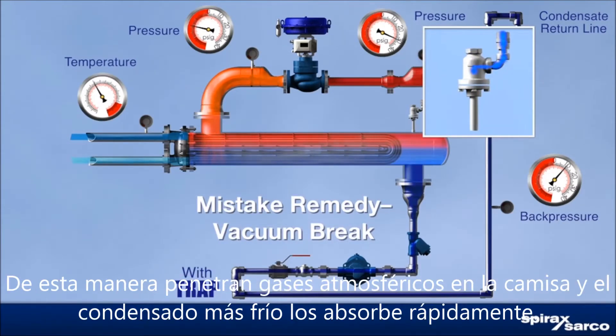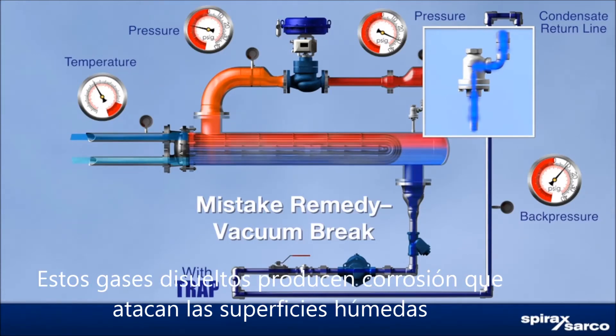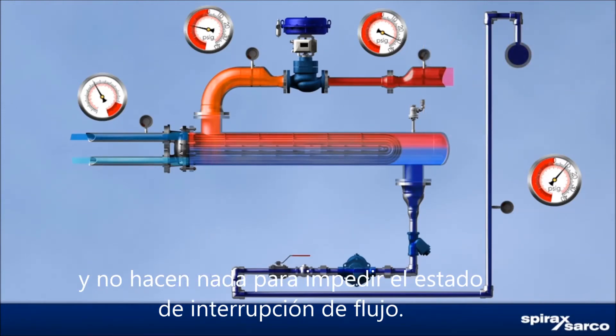This practice introduces atmospheric gases that dissolve readily into the cooler condensate. These dissolved gases form corrosives that attack wetted surfaces, while doing nothing to eliminate the stall condition.